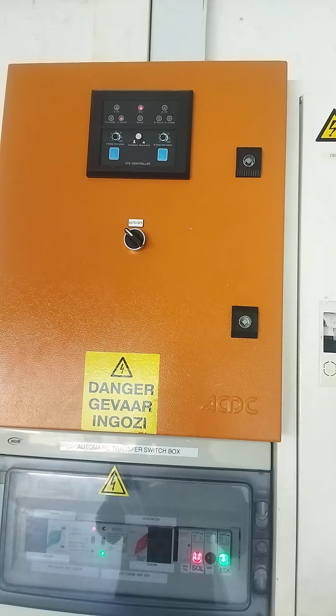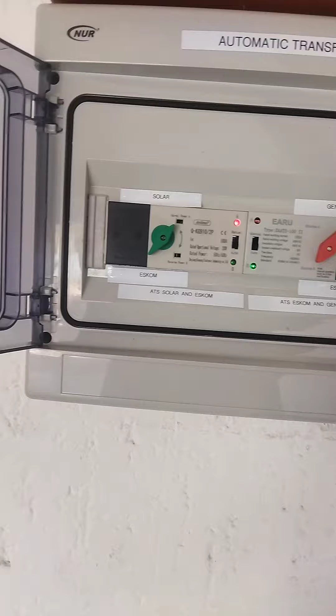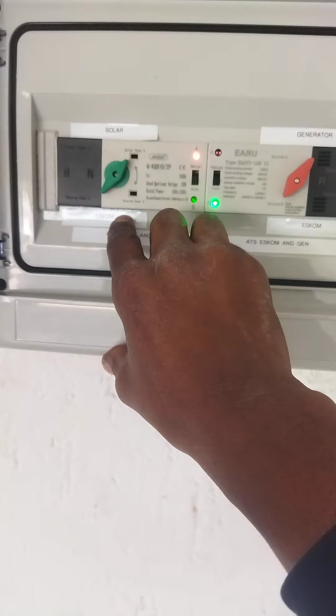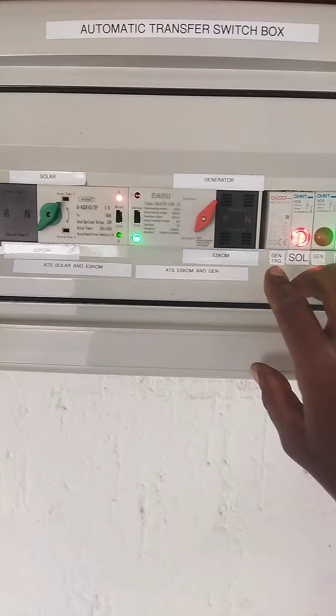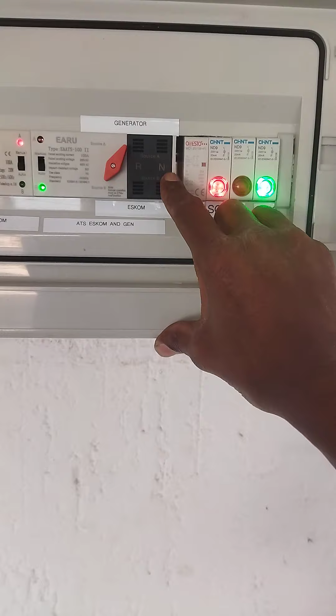And then we've tapped at the top of the changeover switches on both and brought power down into this automatic transfer switch box. So we have two automatic changeover switches here. On top of the changeover switch of Eskom coming in, we fed this changeover switch with Eskom and solar. And then the output of this, we've looped into the Eskom and generator changeover switch, and then out.